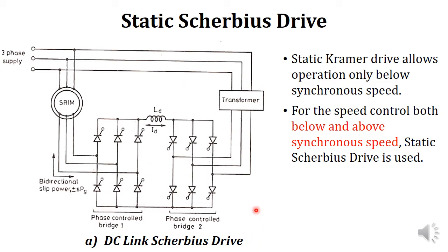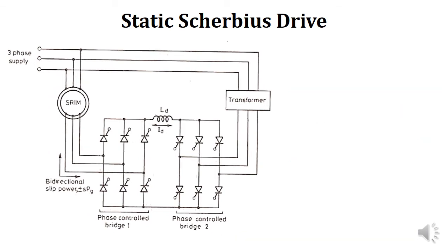Let's consider the circuit diagram of a static Scherbius drive. This circuit diagram very much resembles the static Kramer drive. The only difference is that instead of using a diode rectifier, a phase-controlled bridge is provided. There are two phase-controlled bridge circuits which are connected in anti-parallel — this is known as bridge one and this is bridge two.